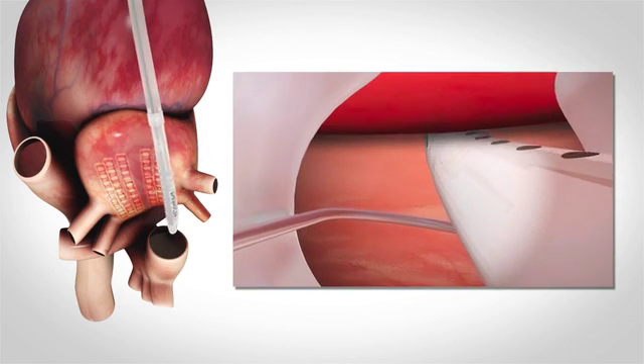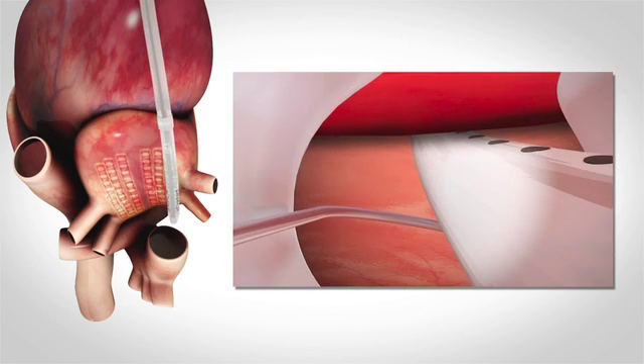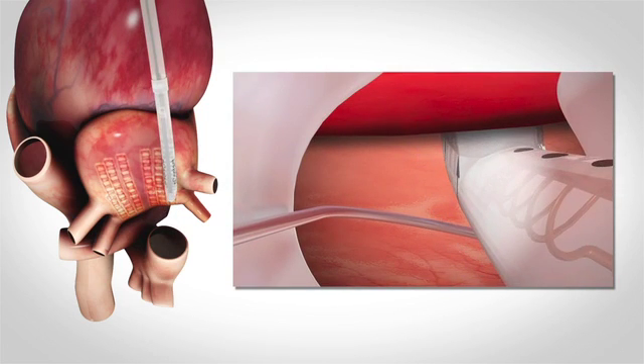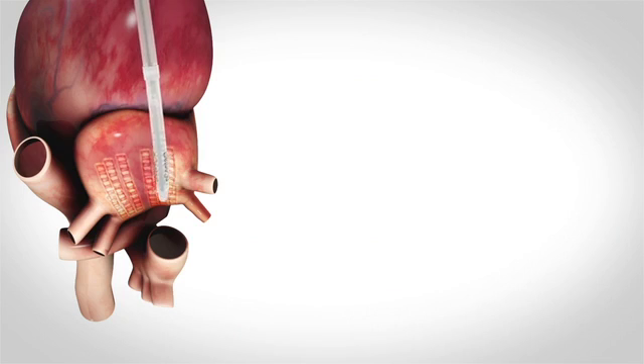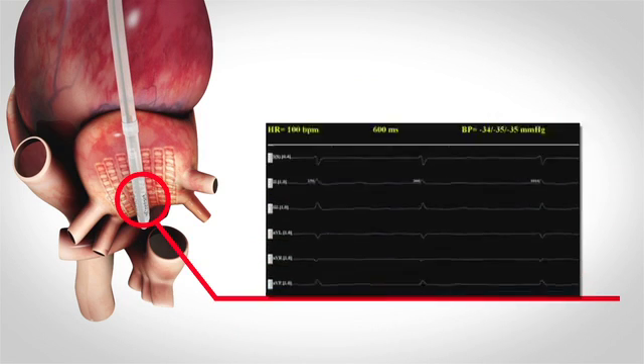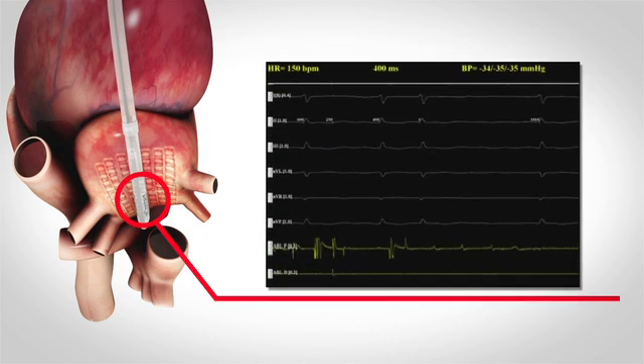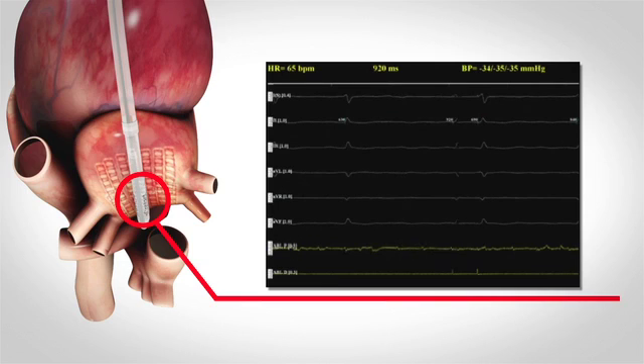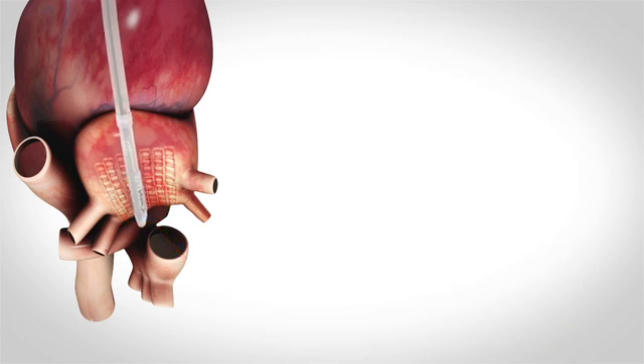You can directly visualize the lesions to make sure that they intersect, but afterwards what you typically will utilize is the sensing function of the EPi-Sense device to make sure that you don't have any signals. If you do have any signals, you're going to want to go out there and repeat the ablation to make sure you've fully isolated and silenced that entire posterior left atrium.